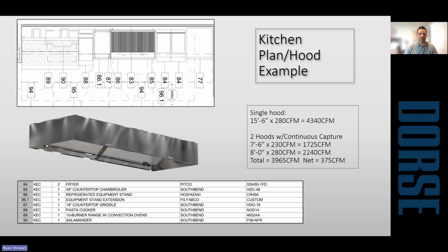So I've divided this up. I have a 7.5-foot hood on the left. It is a heavy duty by appliance classification because of the range. But based on what we have there, I'm comfortable at 230 CFM per foot. We have that wall on the left-hand side, so that's helping with capture and containment. And then on the right side, we have that large charbroiler. That's where you're going to want to be up near the maximum that the code allows. And by doing this two hood approach, we've netted a savings of 375 CFM.